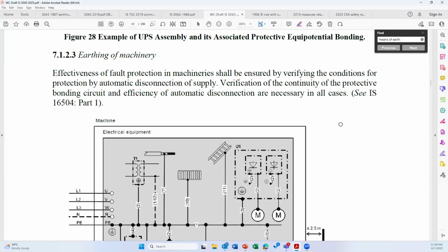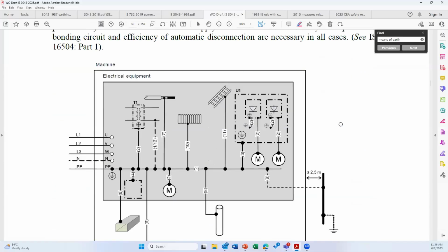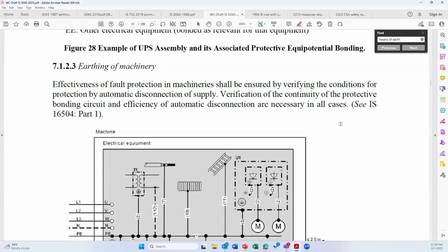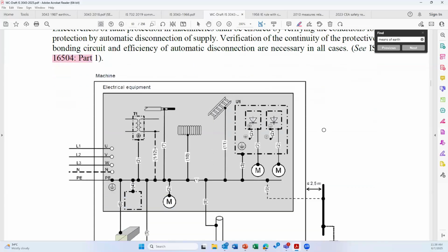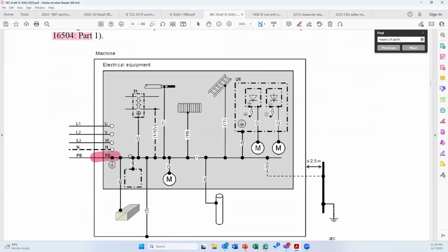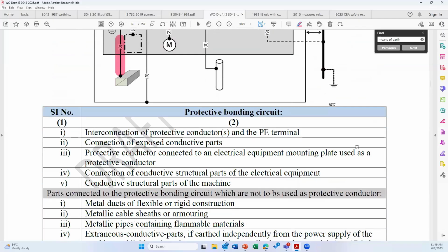You can read it. For machinery, again from the IS standard, IS 16504, how to earth machinery. There is a common earth bus bar. Now you can see here there is a common earth bus bar inside the machinery. All the metallic parts of the machinery are connected to the common bus bar. You can see here, if there is an isolation transformer, the shield or the secondary side of the isolation transformer is also connected to the same common bus bar.